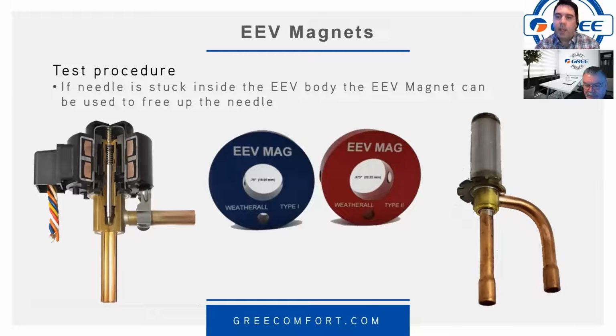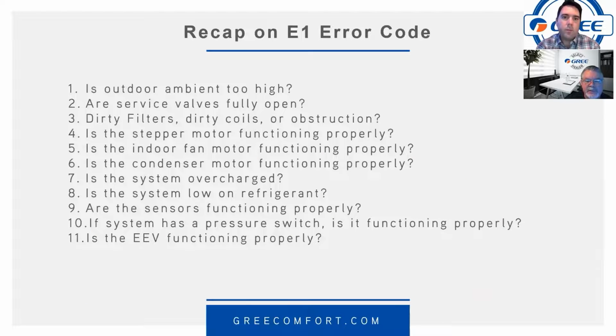Yes, most certainly. And also it's good as a test tool to see if your EEV motor is actually moving or not, or if it's stuck. Yeah. You could open it up fully and listen for that thing to drive down and then open back up again. When you power it up, they drive fully closed and then they'll reopen. So it might be a good idea to cycle that all the way open, but this makes a real easy method for doing that.